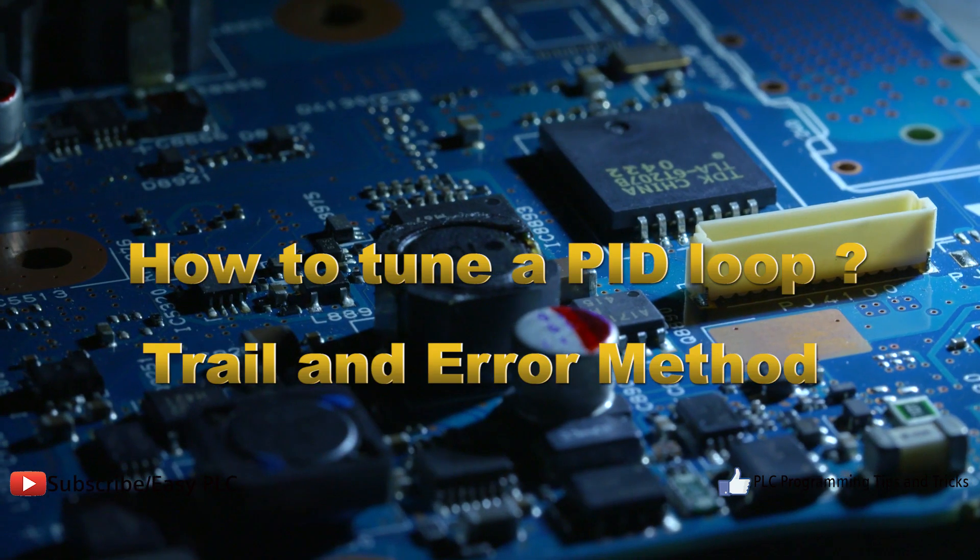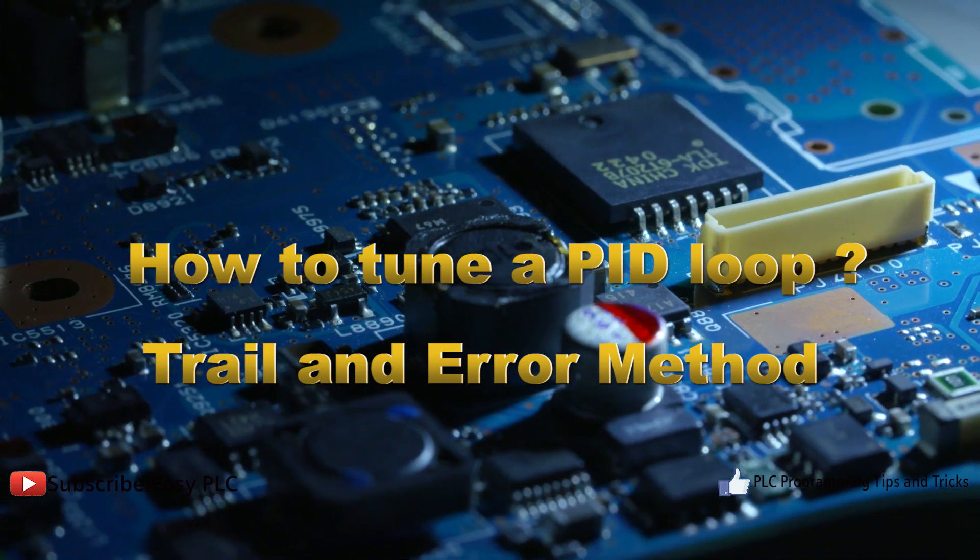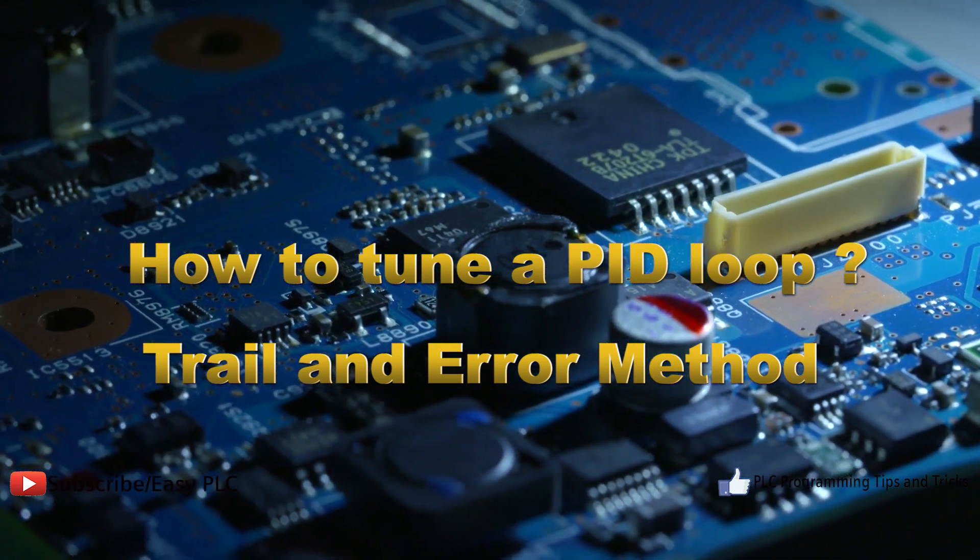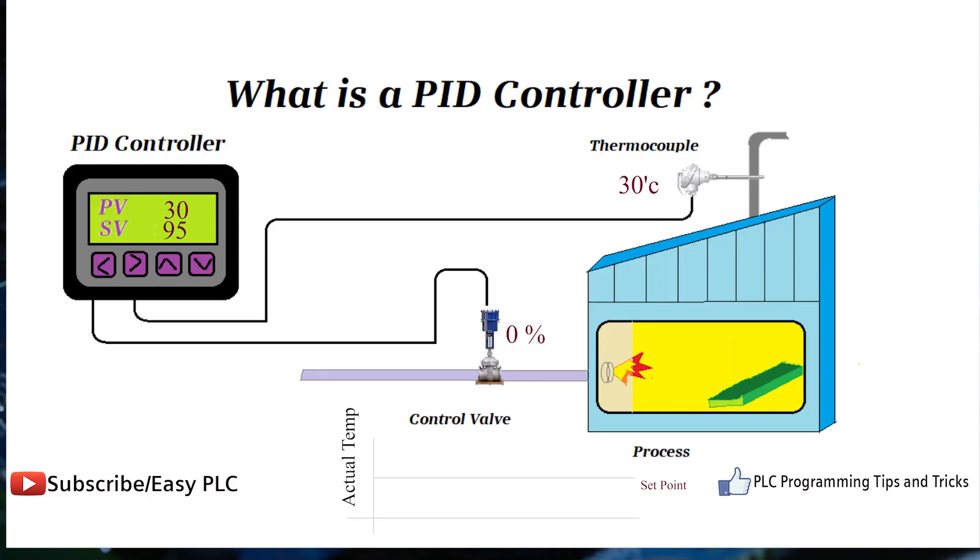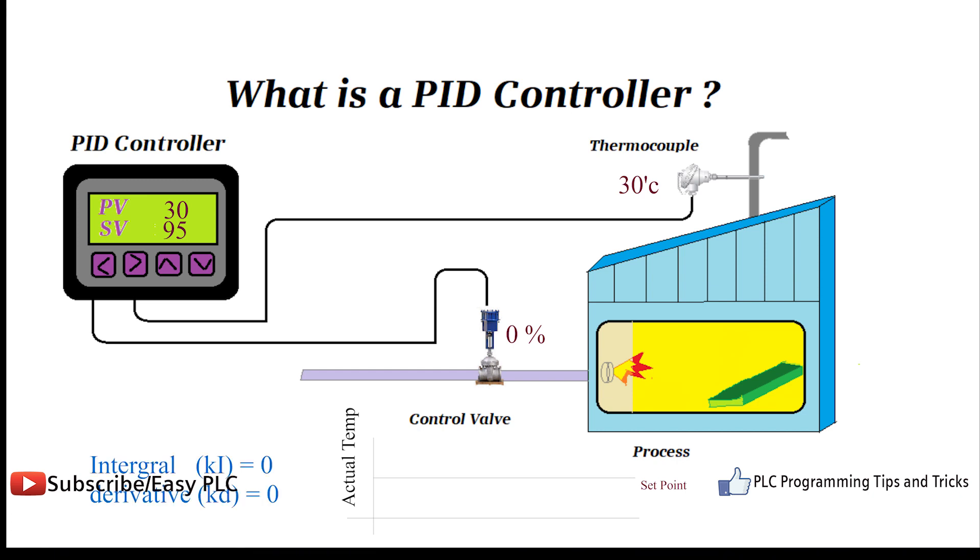Trial and error method: It is a simple method of PID controller tuning. While system or controller is working, we can tune the controller. In this method, first we have to set KI and KD values to zero and increase proportional term Kp until system reaches oscillating behavior.